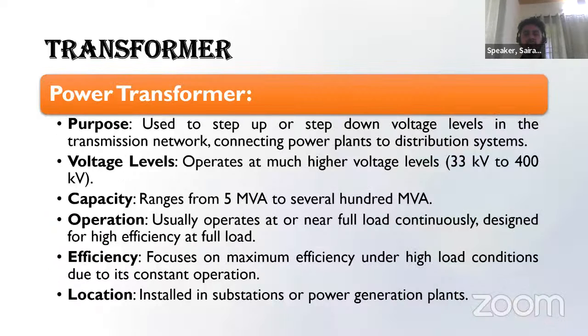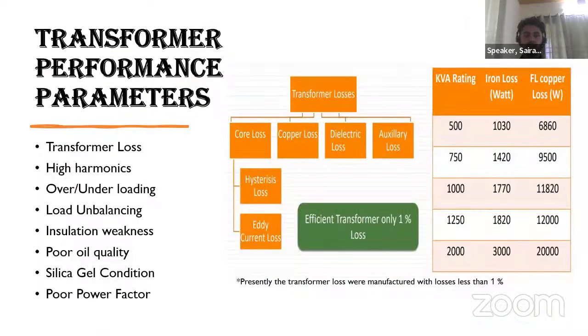Coming to the power transformer, it is used to either step up or step down voltages in the transmission network, from the power plant to the distribution system. The voltage operated will be 33 kV to 400 kV. Its capacity ranges from 5 MVA to several hundred MVA as per the requirements. Power transformers are not like distribution transformers. They are meant to operate effectively at their full capacity. They operate at maximum capacity at a constant load, under higher load conditions. These are installed near substations or power generation plants, where there is a requirement for stepping up or stepping down of voltage levels.